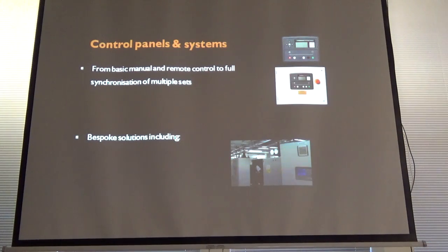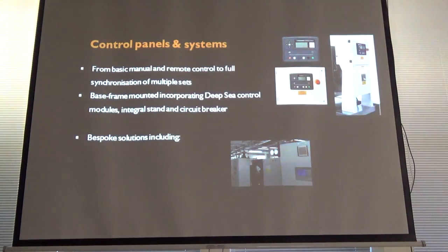You've got deep sea, you've got DEIF, you've got COMAP. It's very much isolation of those systems that needs to be considered as well. You can never connect steel wire armour cables directly to an alternator. Quite frankly, it'll vibrate, it'll work harden, and it'll fracture, it'll fatigue. So you need to have that transition as well with flexible cables.